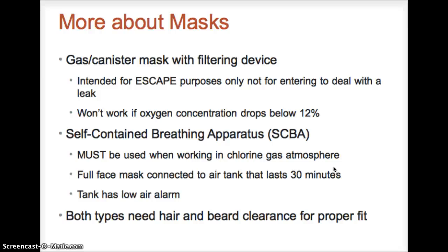It's not meant to keep on and work on a problem. That would be a self-contained breathing apparatus, or SCBA. It must be used when working in chlorine gas atmosphere. The mask is connected to an air tank that lasts 30 minutes, and the tank has a low air alarm, similar to a scuba diving tank, if you've ever done that.